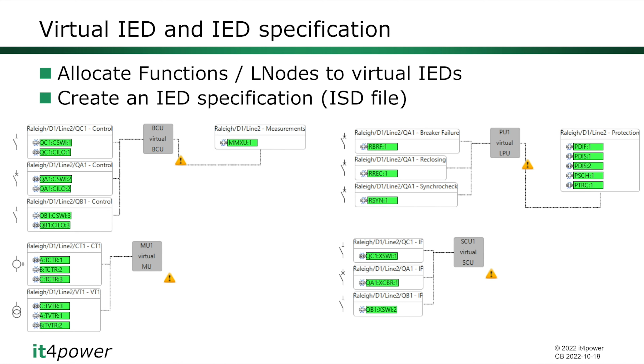You may have virtual IEDs like a merging unit, a bay control unit, a protection unit, or a switch control unit, and define in the specification what functions, and consequently what logical nodes, shall be allocated to these virtual IEDs. Out of that we can create what we call an ISD, a new variant of SCL files, which is an IED specification description file.